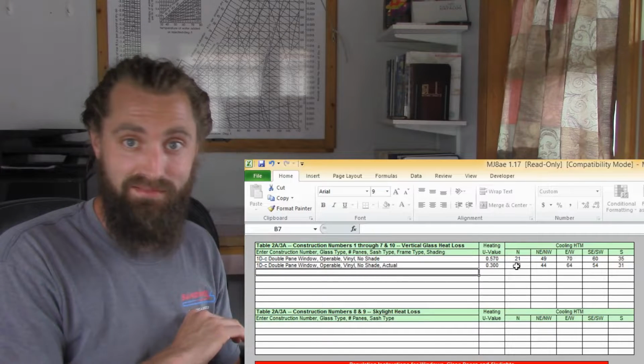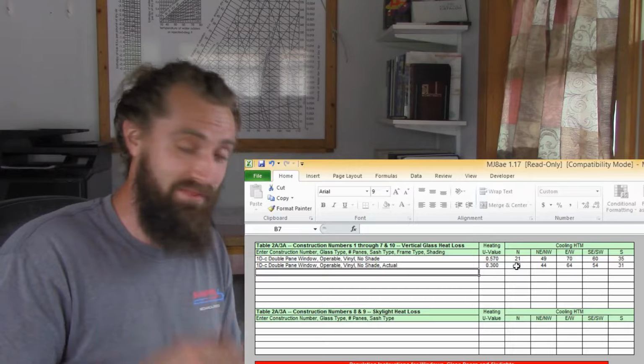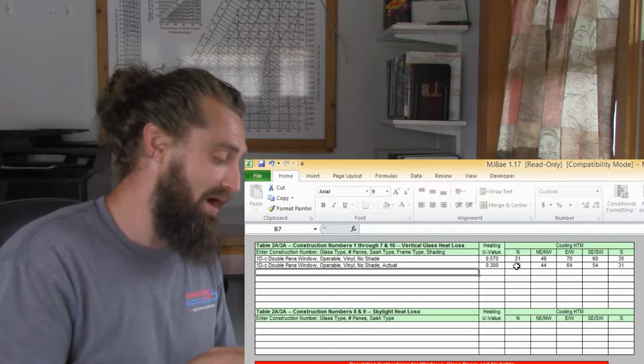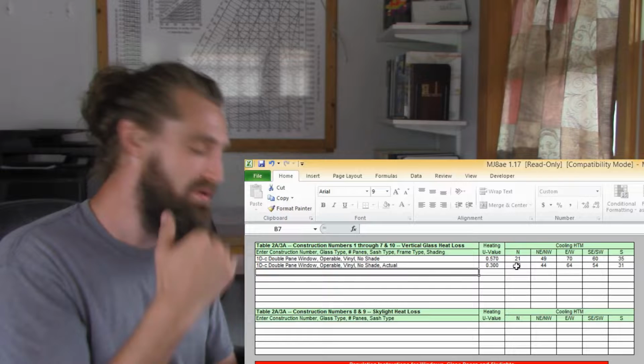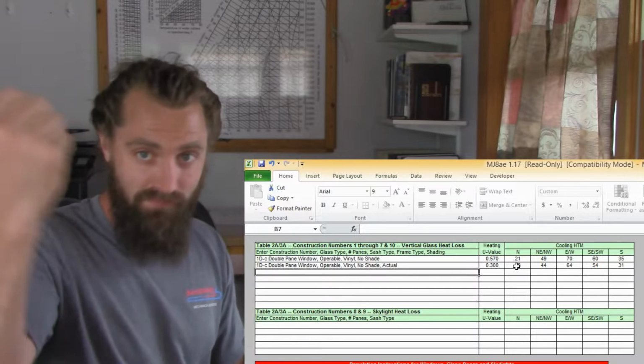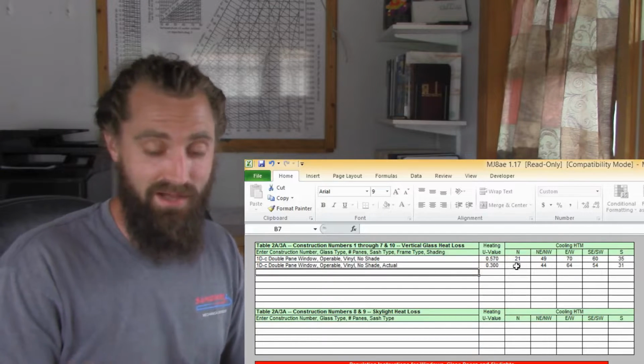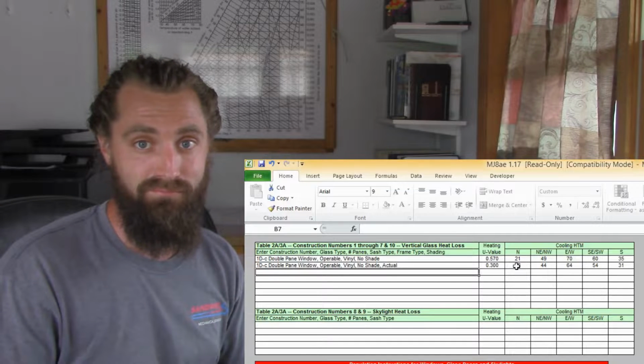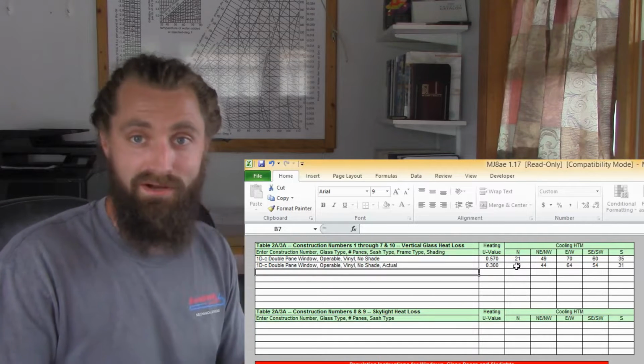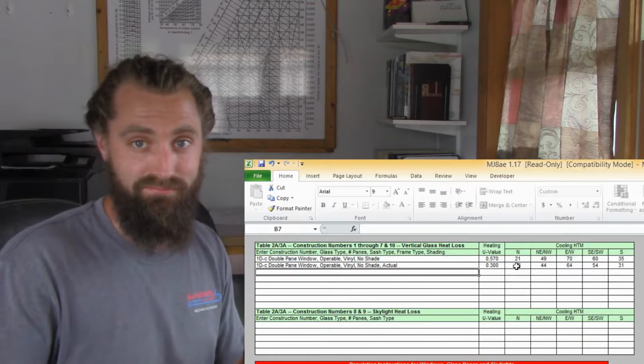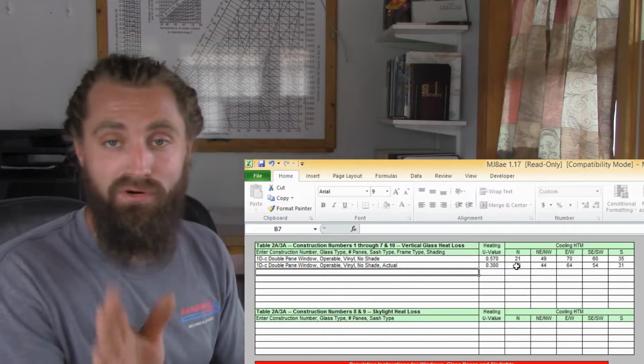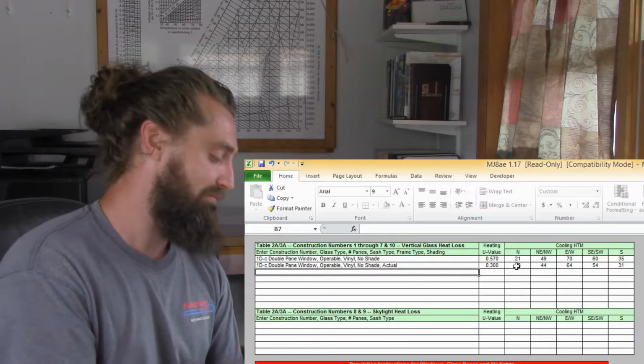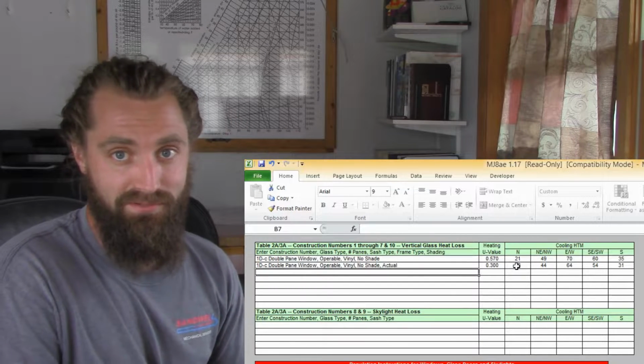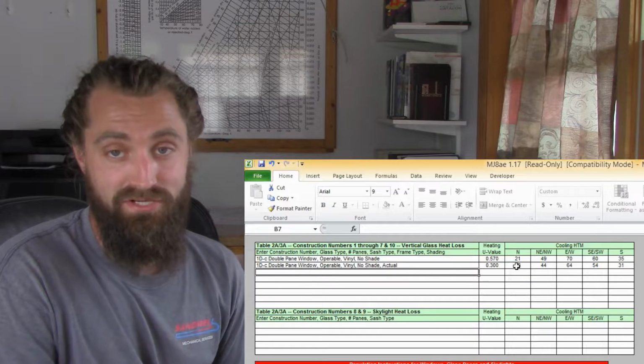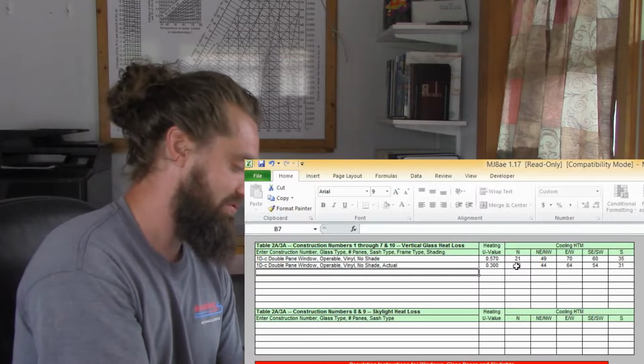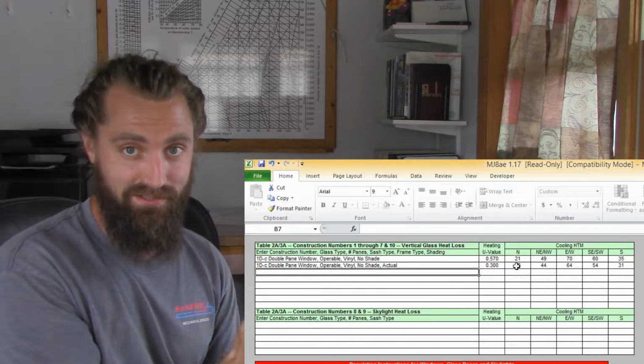I am going to assume that they're going to be open all the time. If they happen to be closed, well then great, but I'm not going to calculate for that unless I know 100% that there's going to be drapery over those windows all of the time. And again, why would you have a window? It makes no sense—you might as well just put a wall there and do away with the window altogether. So we're not going to assume any drapery, curtains, or Venetian blinds over these windows. We're going to say there's no internal shading, no external shading, clear glass for this application.